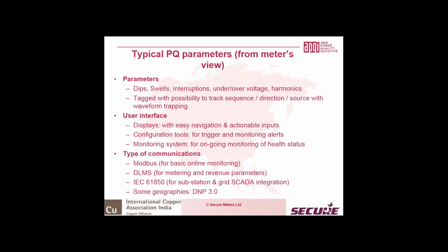So the meter measures dips, swells, interruptions, under and over voltage and harmonics. The importance here again is that certain types of loads generate typical harmonic spectrum signatures, which can help us in identifying the source. Now, this signature can be related to the number of pulses or path of conduction. This signature also is usually linked to the type of device.